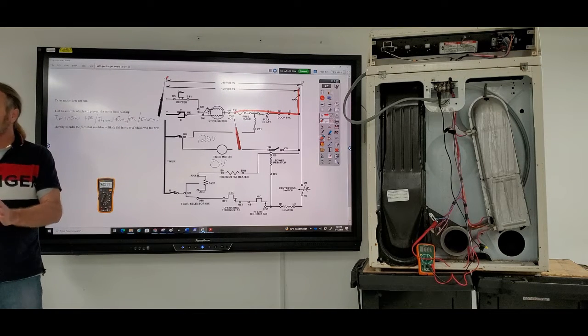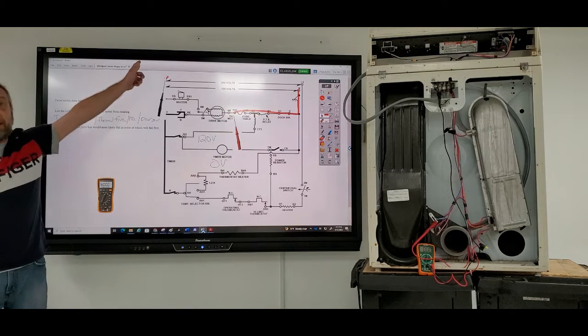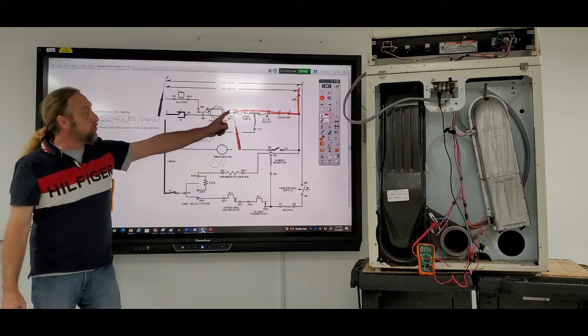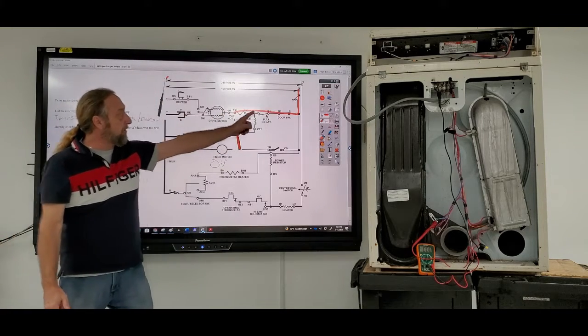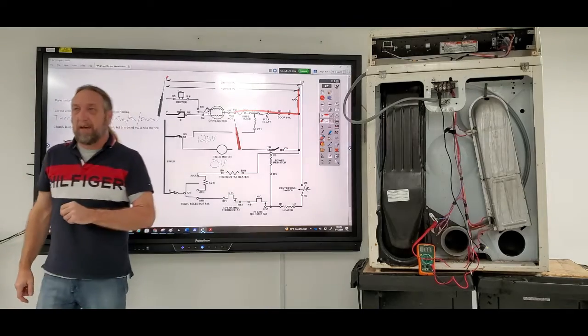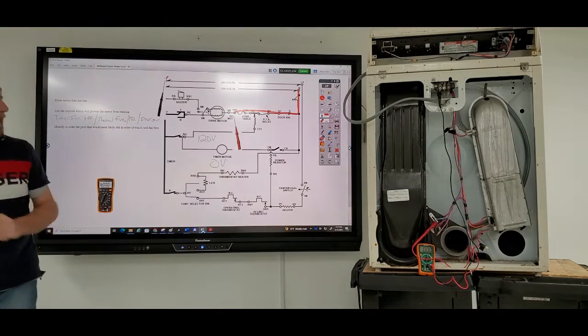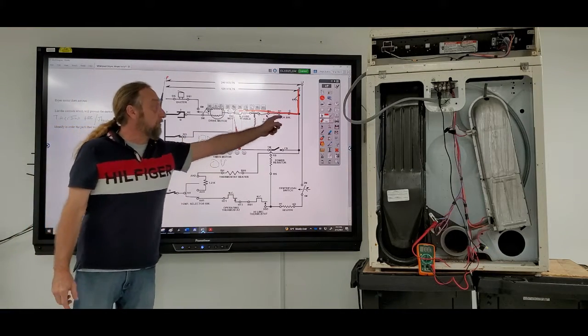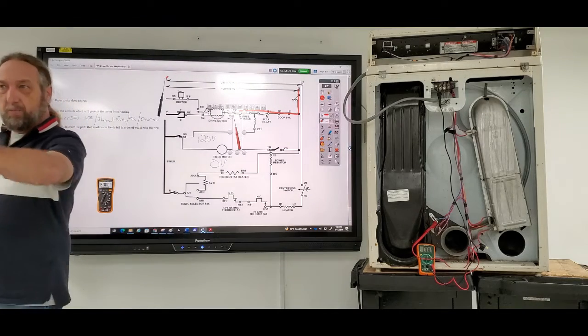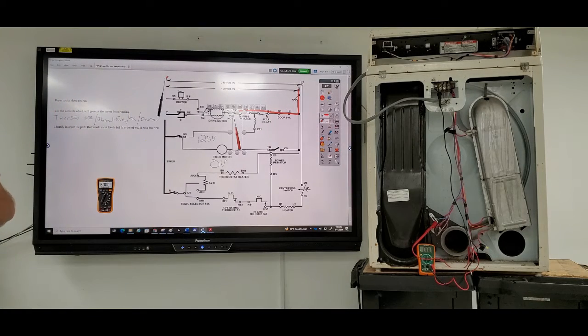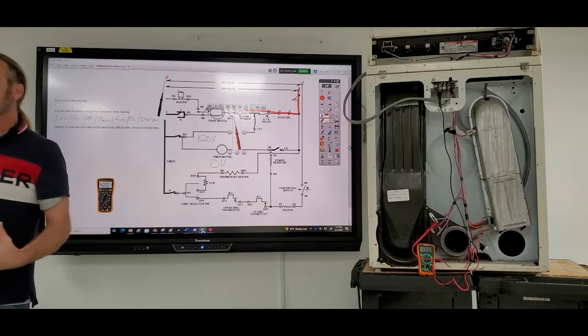In order for me to get 120, I need line 1 and neutral. I'm at line 1, and that's all that is. Neutral is here, which tells me there's neutral up to that point. So I know that the fuse is good, the relay is good, the door switch is good, just by one meter lead movement.